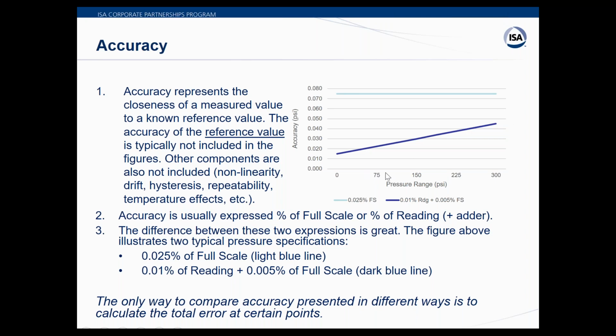But here's a percent of reading and full scale combination. The 0.01% of reading is this slope. As you go from 0 to 300, the tolerance has to increase. But it also has this fixed component of full scale. It's very small, so it basically has an offset. It doesn't start at 0. It starts at the base number, because any percent of 0 is 0, and it begins there and then slopes up.